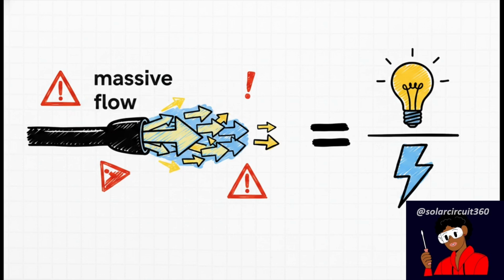Why is this so absolutely critical? Because a massive 10-kilowatt array is going to push a proportionally massive charging current right into a 48-volt battery. Every single piece of your system, the controllers, the batteries, your cables, they all absolutely must be able to handle this massive flow of current. Honestly, ignoring this specific calculation is one of the most common and destructive design errors out there.